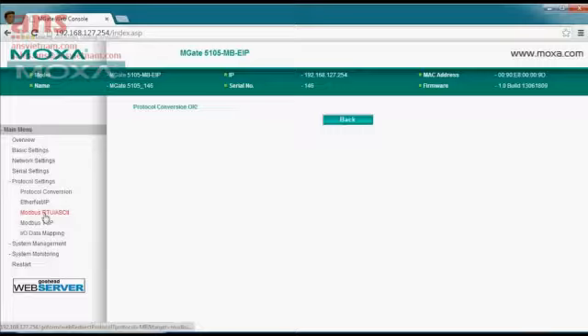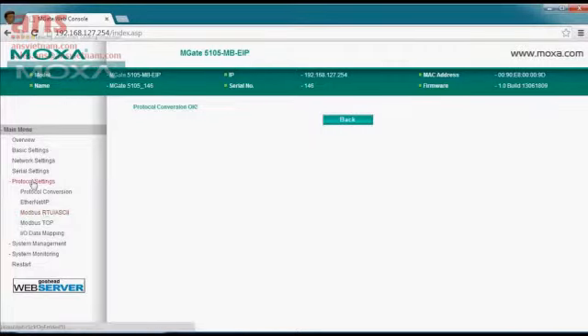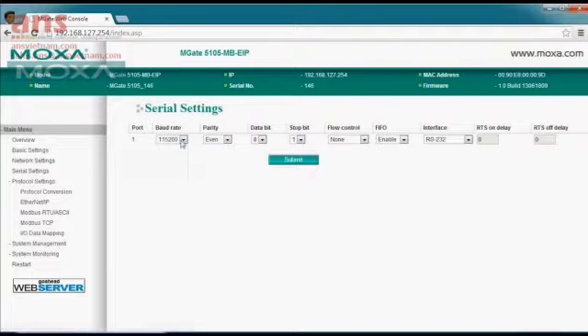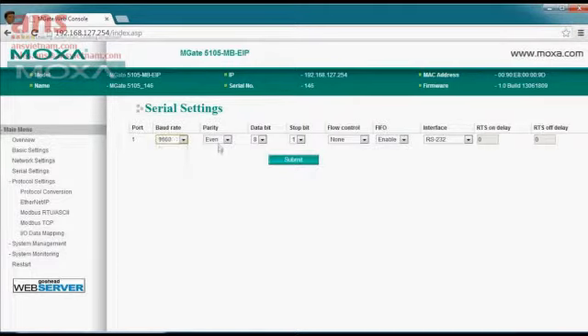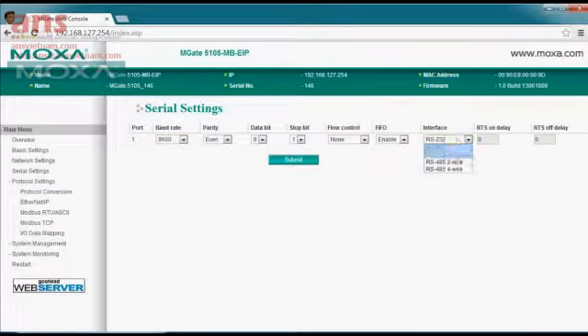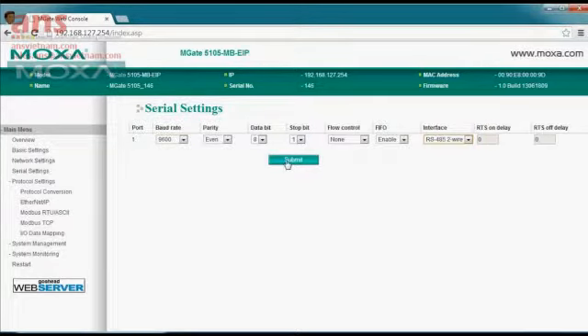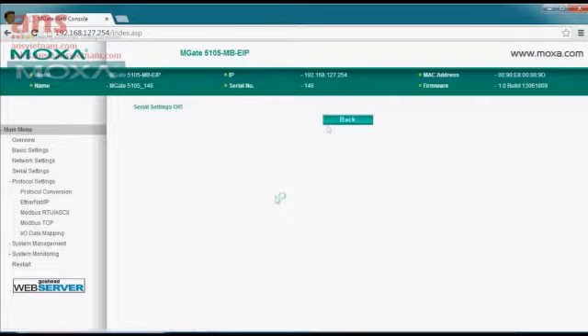Since we've selected a serial connection for our VFD, we need to go in and set the serial port settings. In this case, we're going to select 9600 bits per second, even parity, 8 data bits, 1 stop bit. We also want to change the interface to RS-485. Let's go ahead and make those changes active.